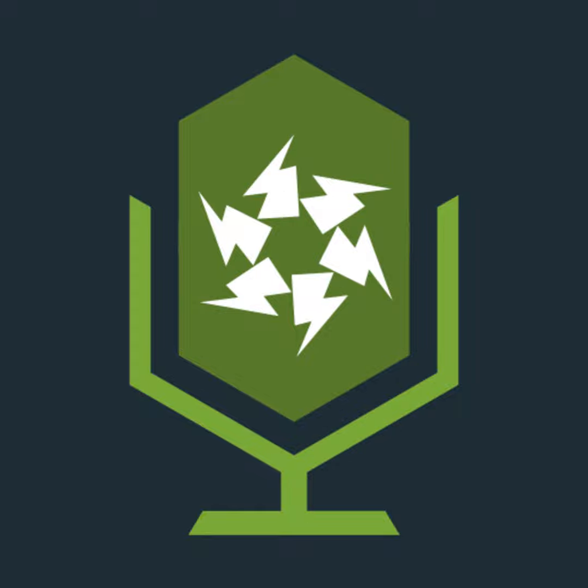And again, we'll touch on this a little bit early, but we'll be getting to earthing and bonding, or more importantly bonding and the voltages as we push through. But this just illustrates how much of the actual location requires protective earthing. All these class 1 items of equipment will become exposed conductive parts of the electrical system, and so Zs values are very essential to make sure that these things will disconnect in the required time frame.